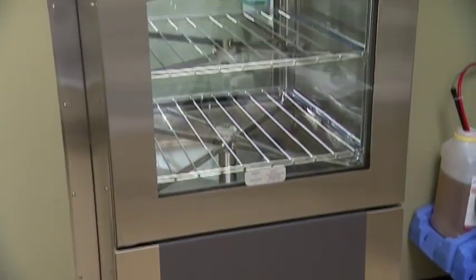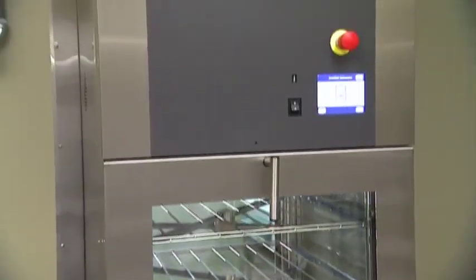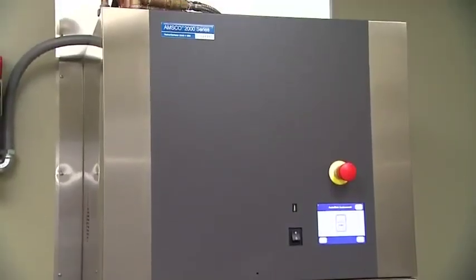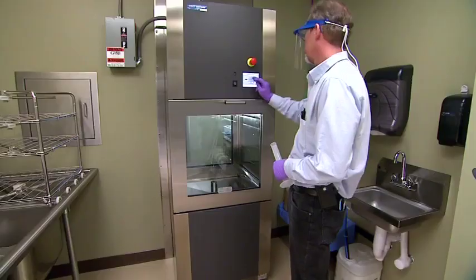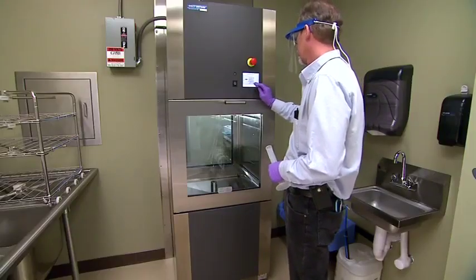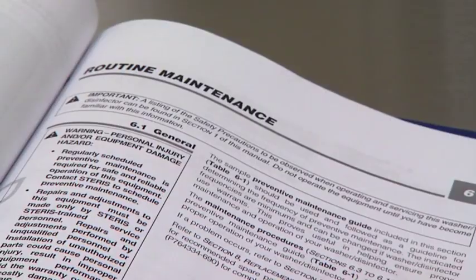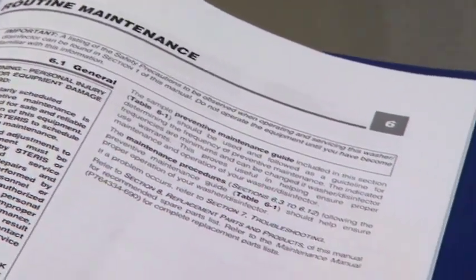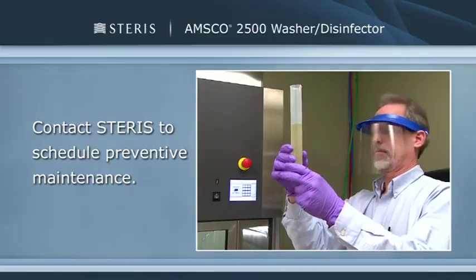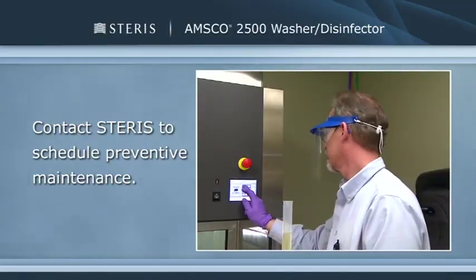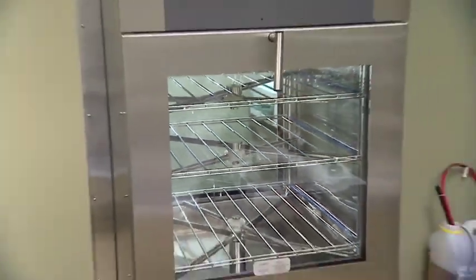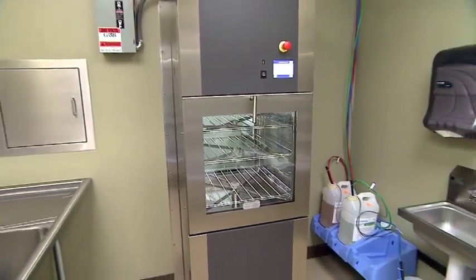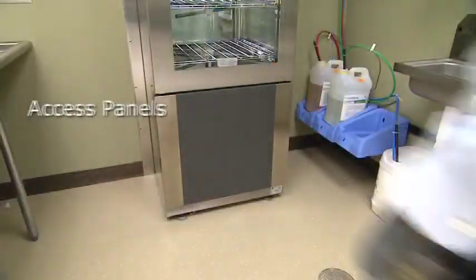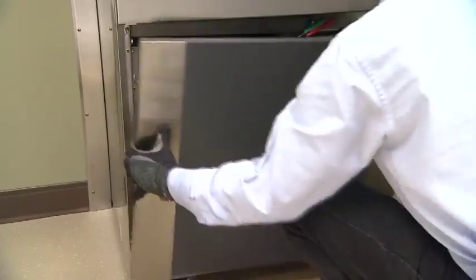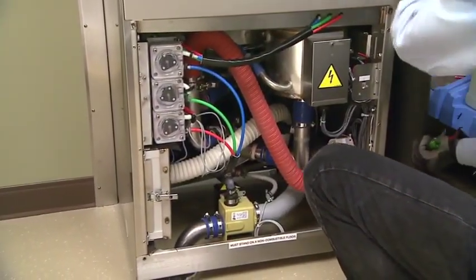To keep your AMSCO 2500 washer disinfector in excellent condition, it's important to clean and maintain it regularly. Remember to let the washer cool down before you perform any maintenance. A maintenance schedule can be found in Section 6 of the AMSCO 2500 Washer Disinfector Operator Manual. Where indicated, some maintenance activities should be performed by a qualified service technician. Let's review the components and their respective maintenance activities that you'll need to perform on a daily, weekly, or as-needed basis.